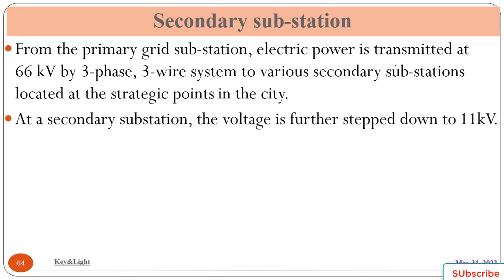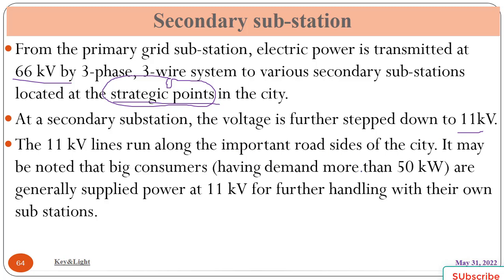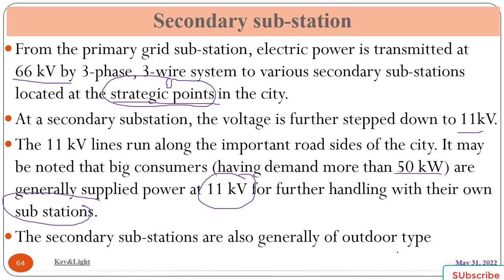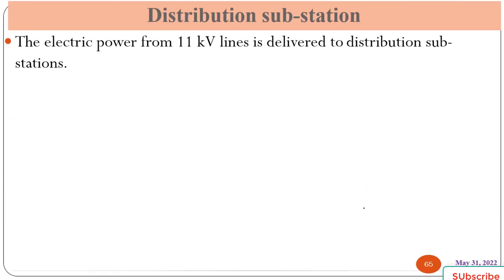The secondary substations: from the primary grid substation, electric power is transmitted at 66 kV, which is stepped down from 220 kV, by three-phase, three-wire system to various secondary substations located at strategic points in the city. A strategic point is a point where the main requirements are. At a secondary substation, the voltage is further stepped down to 11 kV. The 11 kV lines run along the important roadsides of the city. It may be noted that big consumers having demand more than 50 kilowatts are generally supplied by the 11 kV lines for further handling with their own substations. The secondary substations are also generally outdoor type.